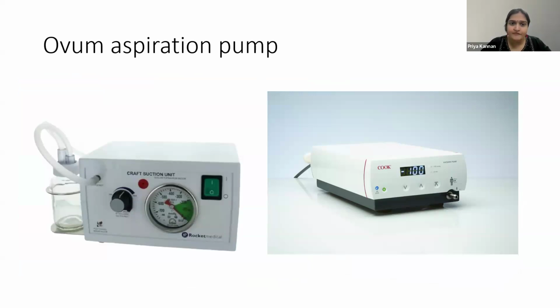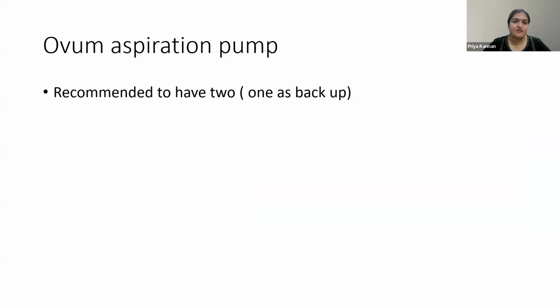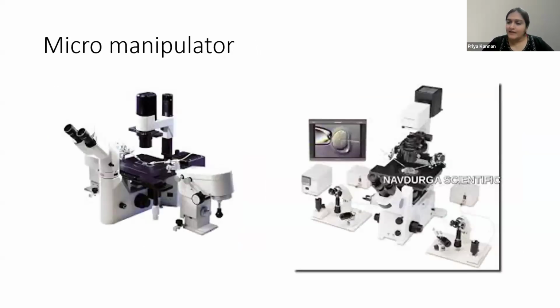This is another of the equipment that I would definitely recommend that you have a backup one. If you don't have a backup, your clinician should be skilled enough to use a syringe to aspirate through the needles when this comes off. So it is also something that I would definitely recommend that you have a backup, or have a friend nearby who will be willing to loan you the ovum aspiration pump when there is a trouble with yours. As I said, recommended is 2. It is not mandated, but I feel it's something that you should have one as a backup. Otherwise, have a friend nearby. Keep your nearby fertility center as your friend.